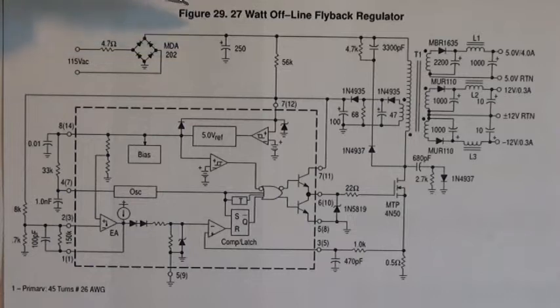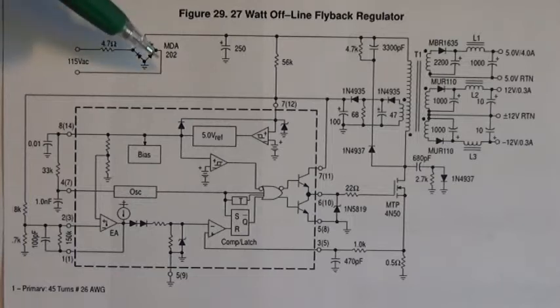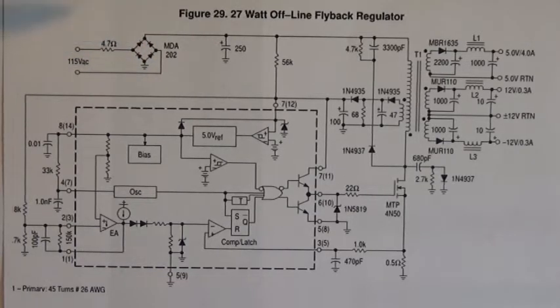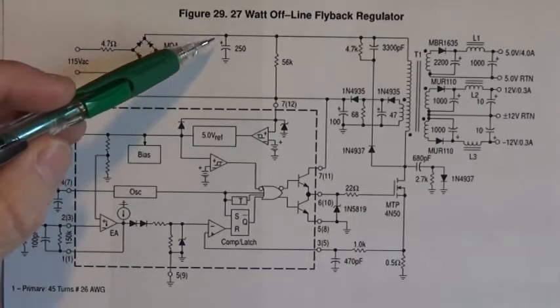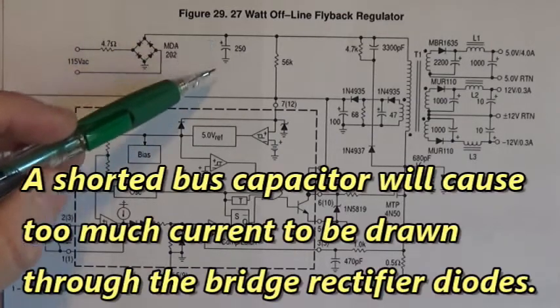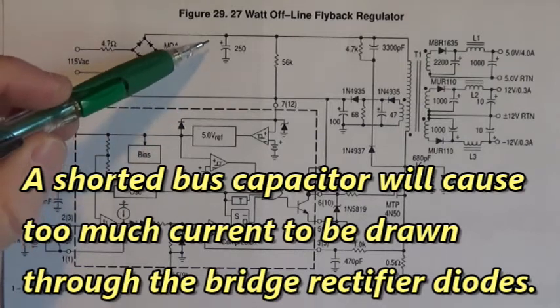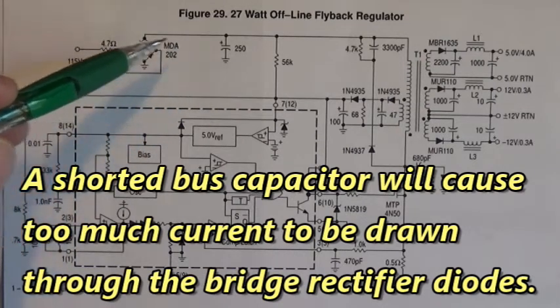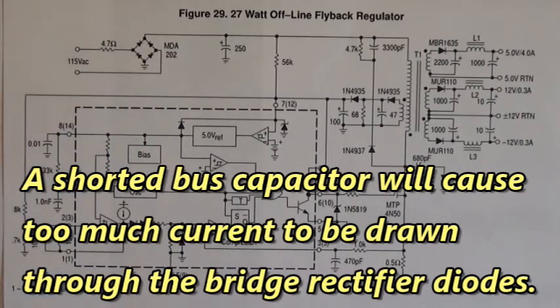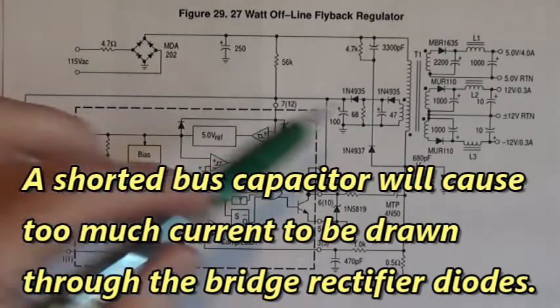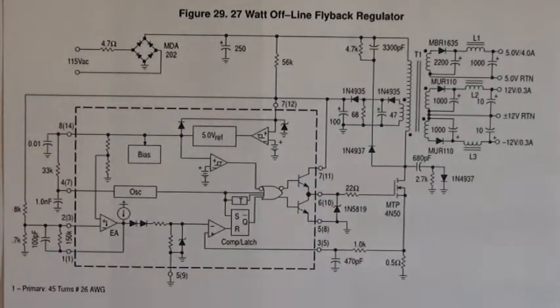Going back to the power supply input, I've seen the bridge rectifiers blown open, shorted, and destroyed. And I've seen the bus capacitors short and blow open. And that will be another cause of this circuit not powering up. So don't forget to check that right there.